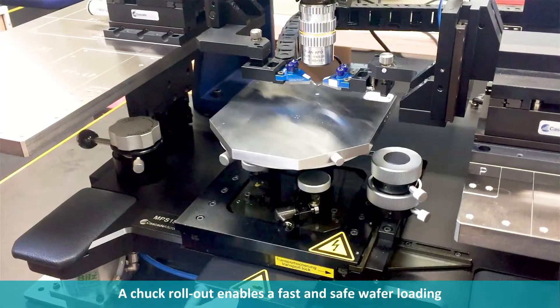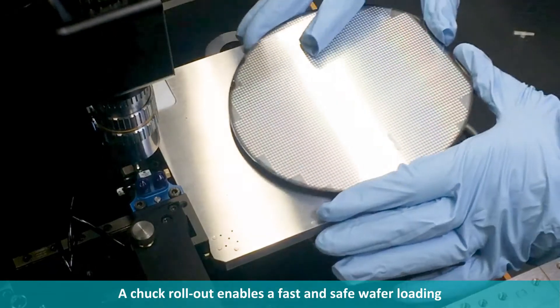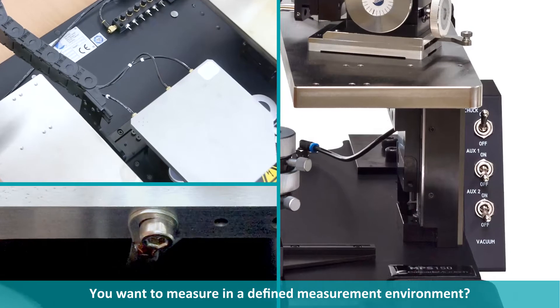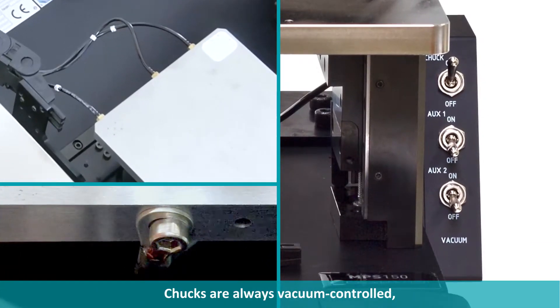A chuck rollout enables a fast and safe wafer loading with probes or probe cards. You want to measure in a defined measurement environment? No problem. Chucks are always vacuum controlled, isolated from ground, and include a jack that can be used to ground or bias the chuck.